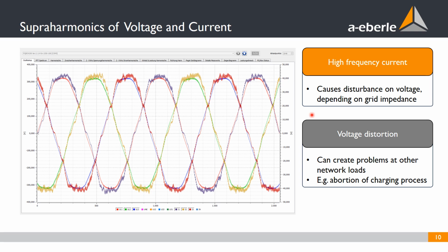When you have a look at an oscilloscopic view with this high sampling frequency, you can see these high frequency ripples on top of the current and the voltage. Just from the mechanics of how the distortions are spread, you can say that these high frequency currents are produced by the charging stations, and they are causing a disturbance level on the voltage just over the grid impedance of the connection point.